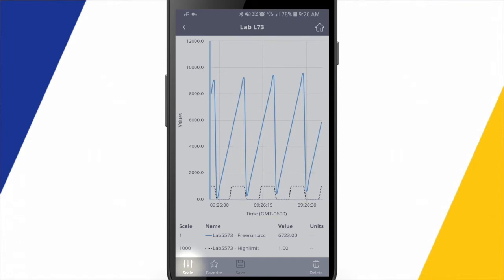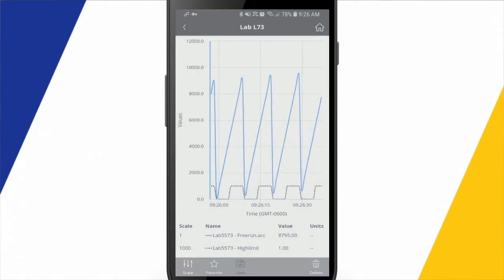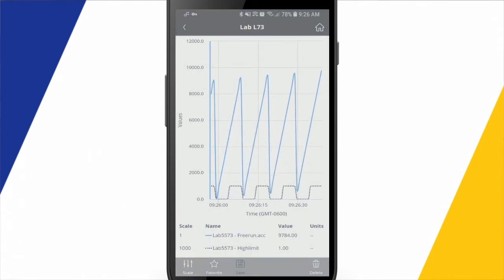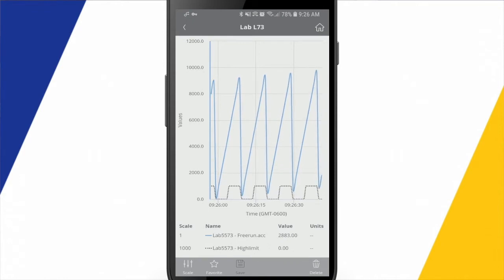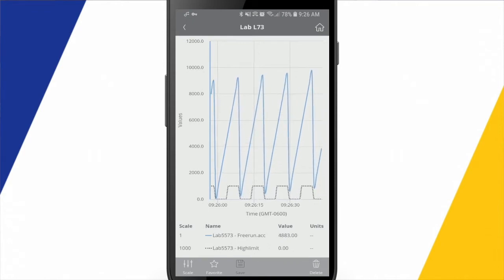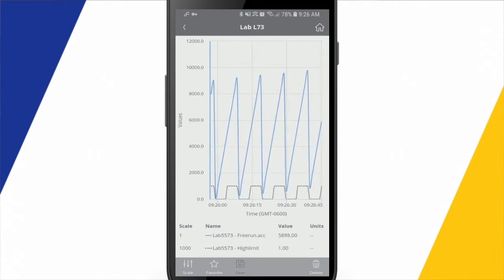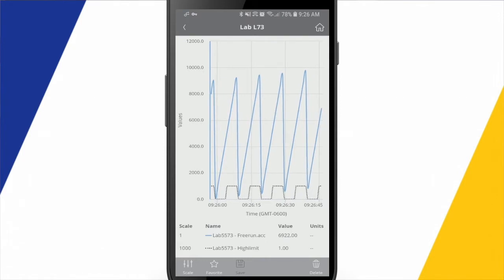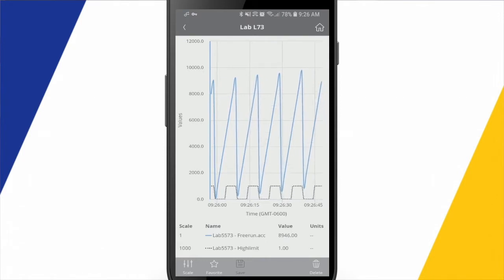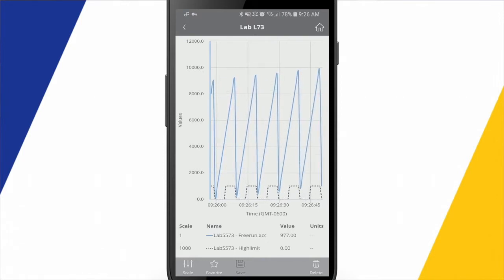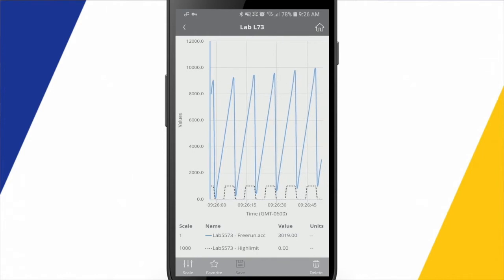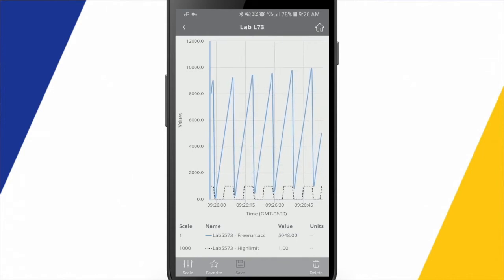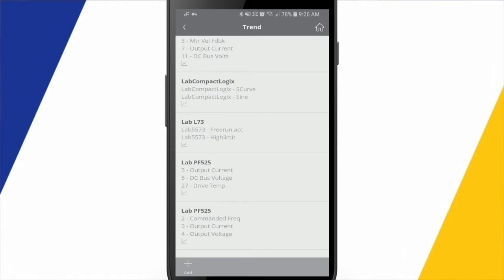Down in the lower left, I can change the scale. So what I've done right now is, by default, everything comes in as a scale of one. Again, being that the high limit is only a bool, and it can only ever have a value of a zero or a one, I change the scaling to 1,000 so that if it's a one value, it'll show as 1,000 on the trend just to give us a little more visibility.